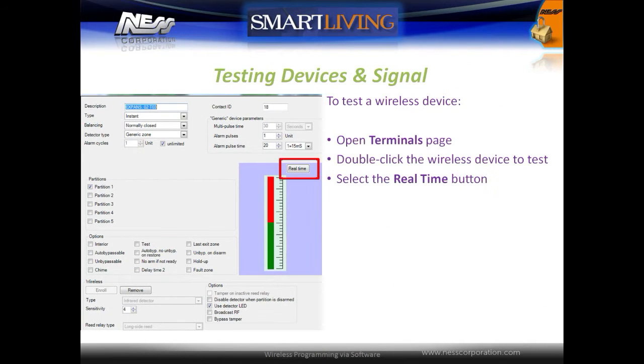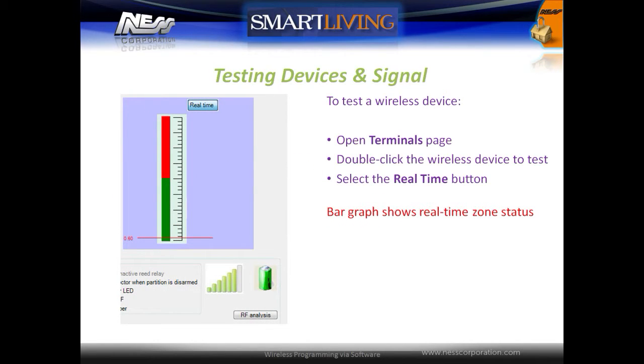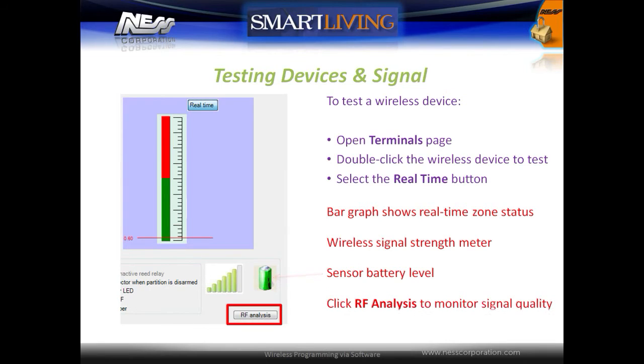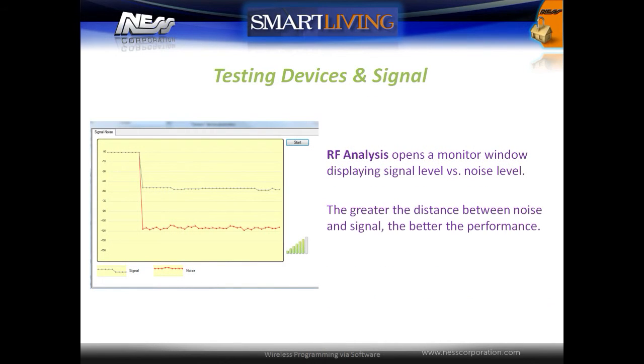To test a wireless device, open the terminals page, double click on a wireless terminal to test, and then select the real time button. The bar graph will show real time zone status as the zone is triggered. Signal strength is indicated by a wireless signal strength meter, and the sensor's battery level can also be observed. The RF analysis button will open an analysis window to monitor signal quality. The RF analysis monitor will show a signal level at the top and a noise level at the bottom — the greater the distance between the two signals means the better the signal quality.